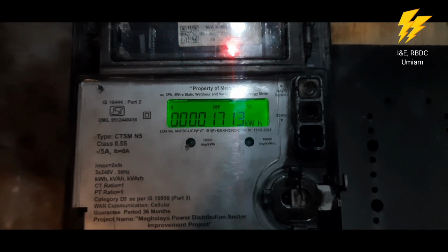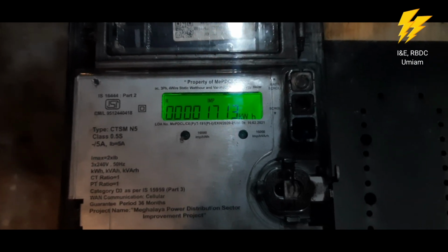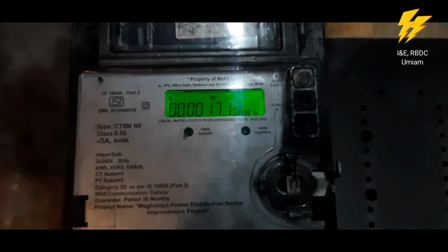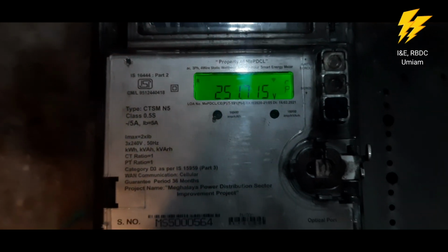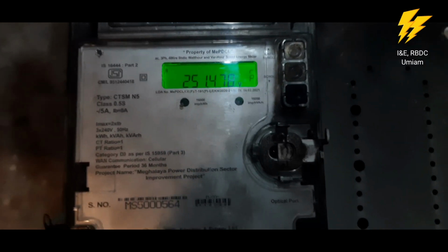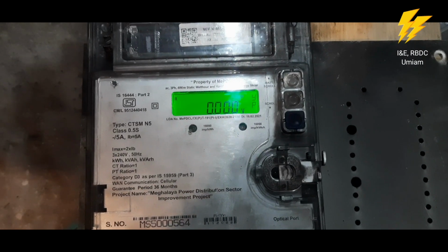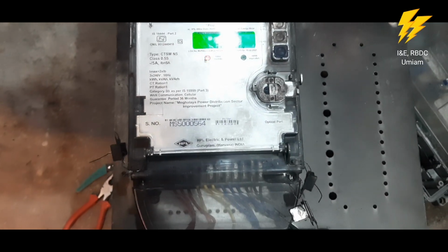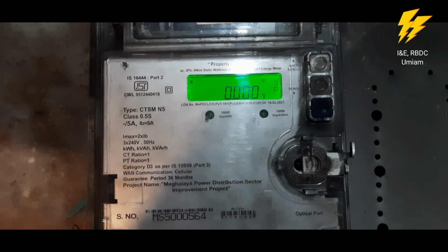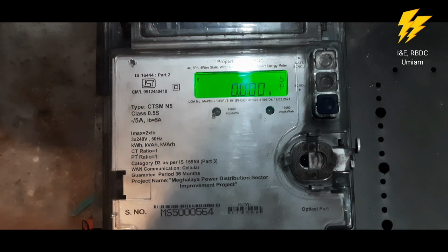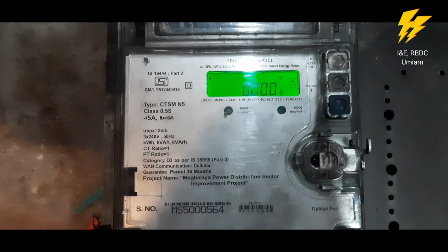The very first one is the present kWh, and the second is the R phase voltage, which we will see now. How much is the voltage? Yes, it is 251.695, which is good enough. It keeps fluctuating because this is an instantaneous value. It doesn't mean that it'll be fixed, but 251 is a very high voltage though. Since it's for study purpose only, I did not connect anything in Y phase, so the voltage here is 0. Had I connected it, it would show something.